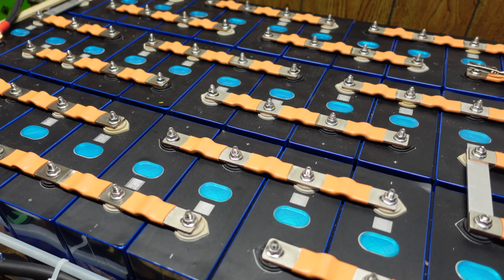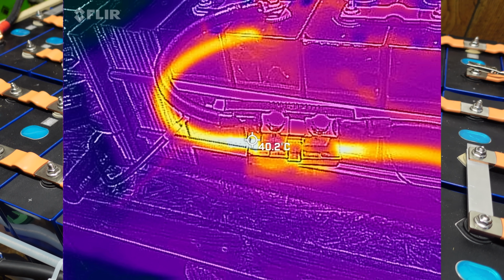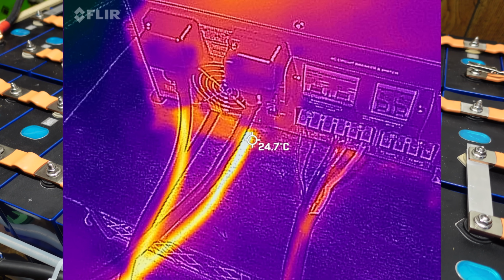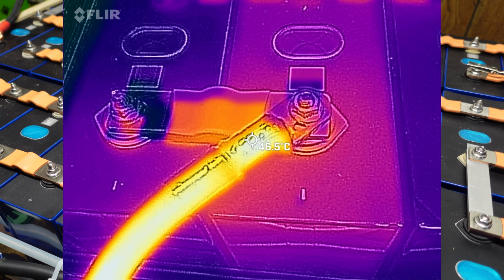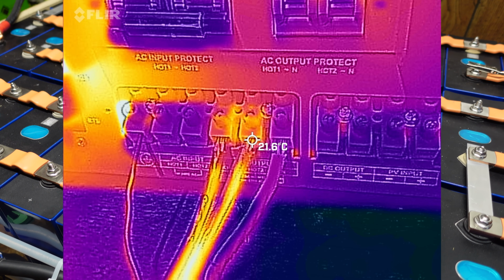So the only thing that I really question is why that fan is running constantly in there. It should be idling around 185 watts without that fan running. So taking a look at some of the thermal pictures here, most of the heating occurred on the cabling at or where the terminal lugs were crimped on. So here you can see we have 40 degrees Celsius at the shunt crimp connection, and the hottest crimp at the inverter was 25 degrees Celsius. And here's where the negative connected to the battery post was at 46 degrees Celsius. There was no thermal problems at all in the terminal block of the inverter. That maxed out around 22 degrees Celsius.